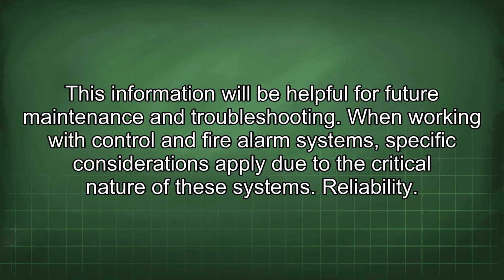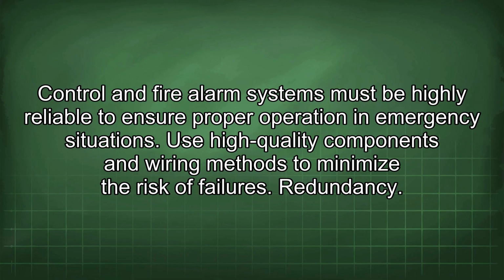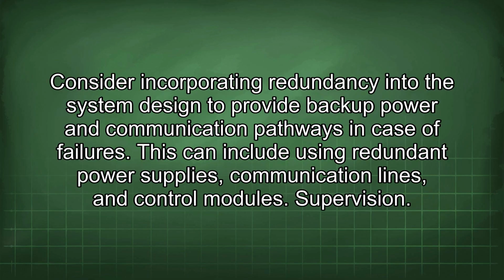When working with control and fire alarm systems, specific considerations apply due to the critical nature of these systems. Reliability. Control and fire alarm systems must be highly reliable to ensure proper operation in emergency situations. Use high-quality components and wiring methods to minimize the risk of failures. Redundancy. Consider incorporating redundancy into the system design to provide backup power and communication pathways in case of failures. This can include using redundant power supplies, communication lines, and control modules.